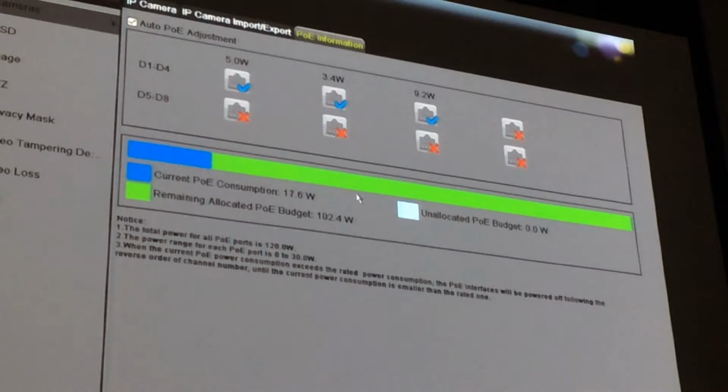Not my fault. You had a power outage. So then they'd have to do the calculation here and say, look, I've got to do at least 5 watts. Here, you see this one is 9 watts. So just pretend if I had to do 9 watts across 8 channels, plus the DVR, that's how big a UPS I need. So if they ever ask you, you have to know all this information and calculate it, okay?